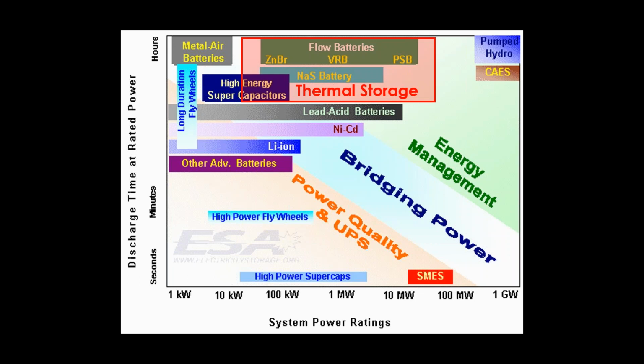Thermal storage covers a large span, from discharging in minutes to hours, and from very small systems to very large ones. Because 35 to 40% of peak electric draw on a hot summer day is the instantaneous creation of cooling, thermal storage is the easiest and by far the largest movable load in a building. So in a zero energy building, storing some energy—especially cooling energy, if there's cooling associated with it—is the low-hanging fruit.